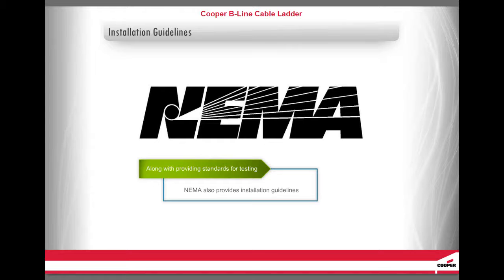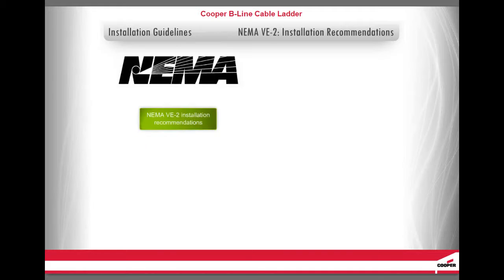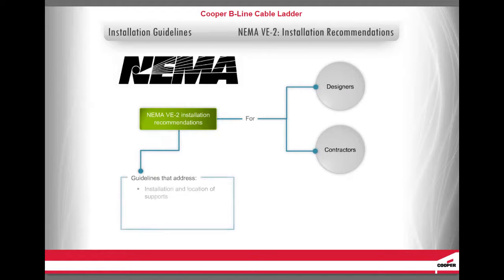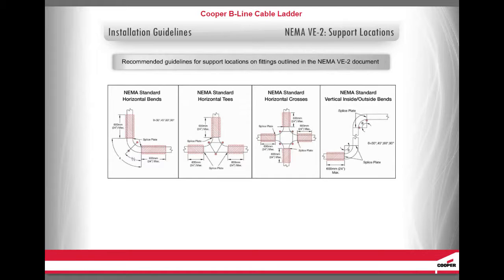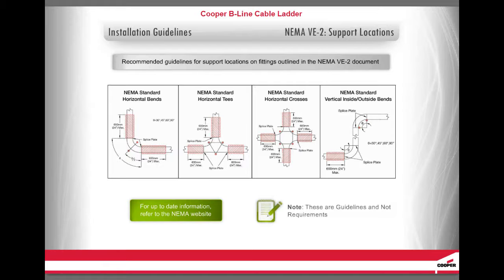Along with providing standards for testing, NEMA also provides installation guidelines. The NEMA VE2 installation recommendations are for designers and contractors. They are guidelines that address installation and location of supports, field modifications, grounding and bonding, as well as handling and storage. The NEMA VE2 document is free and publicly available for download on the NEMA website. The recommended guidelines for support locations on fittings are outlined in the NEMA VE2 document — for the most up-to-date information, refer to the NEMA website. Note: these are guidelines and not requirements.